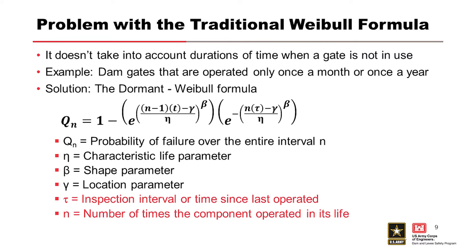A problem with the traditional Weibull formula is that for a lot of our project, particularly flood control dams, the machinery is not used on a regular basis. We like to see the machinery exercised at least monthly. Sometimes that's not possible. Some I've seen where quarterly is pretty common or even annually.